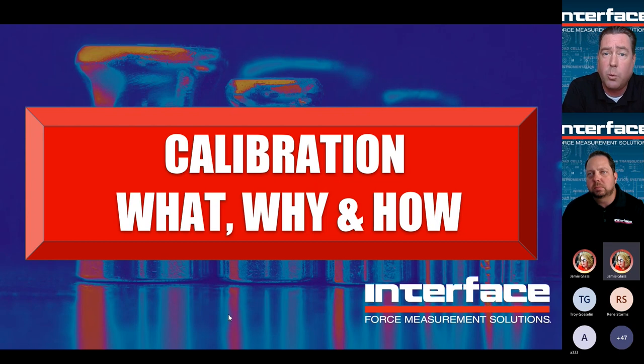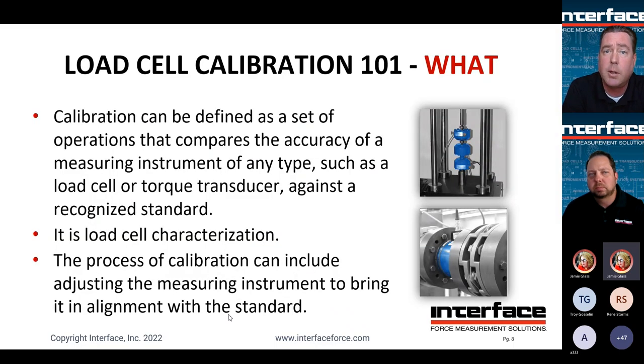So, kind of the basic what, why, and how behind calibration. Load cell calibration 101, kind of the what. Loosely, it can be defined as the set of operations that compares the accuracy of a measuring instrument of any type, such as a load cell or torque transducer in this case, against a recognized standard. A common misconception is that there's some sort of adjustment process that goes into a lot of these calibrations for load cells, when in fact it should be more commonly referred to as almost a characterization, where we're actually characterizing the performance of a load cell or torque transducer against that known standard.